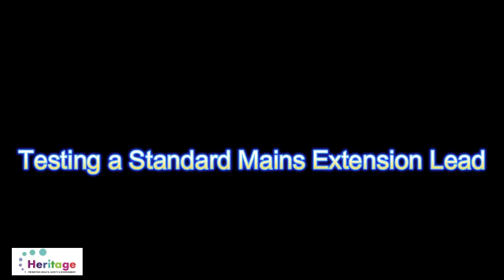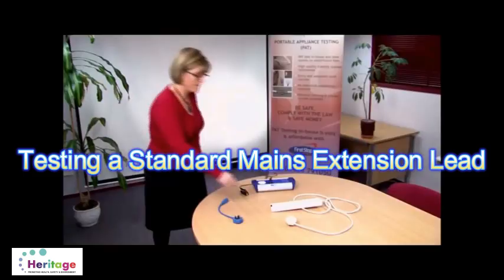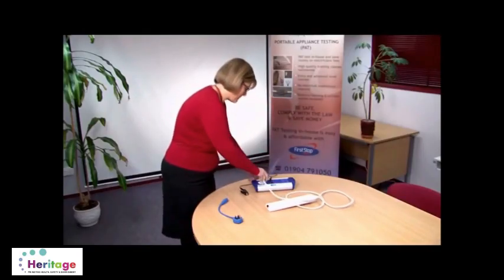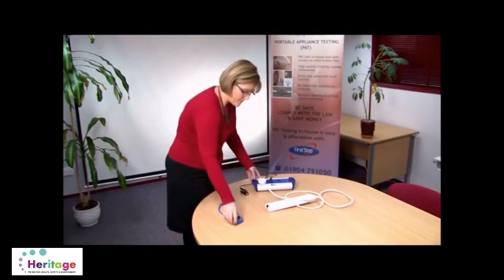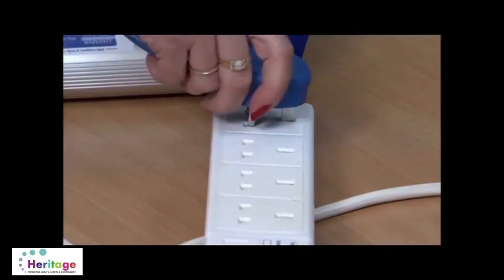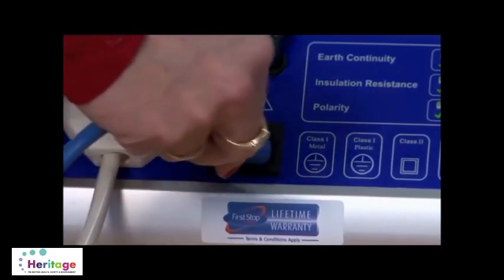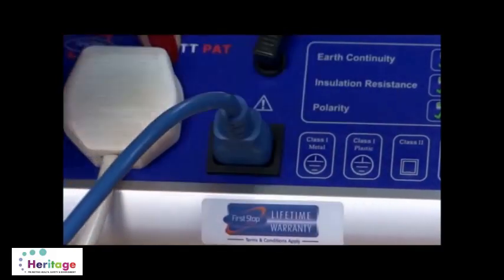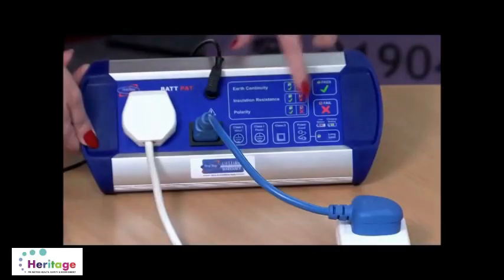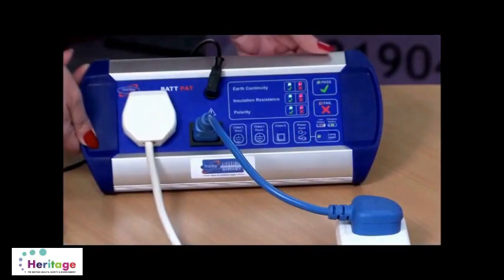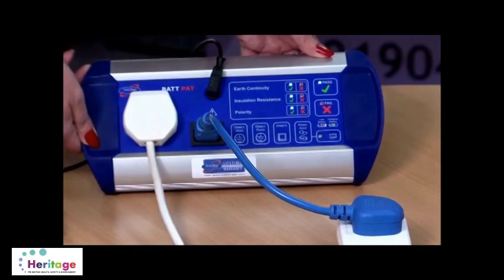Testing a standard mains extension lead. Plug the mains extension lead into the BAT-PAT. Connect the short IEC lead to the socket of the mains extension back into the PAT tester as shown. Press the power cord button and wait for the BAT-PAT to display the results of the earth continuity, insulation resistance and polarity tests.